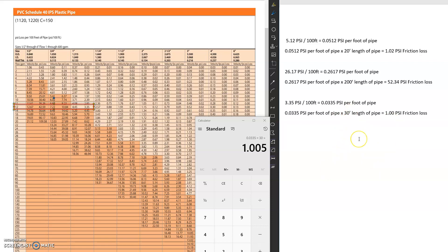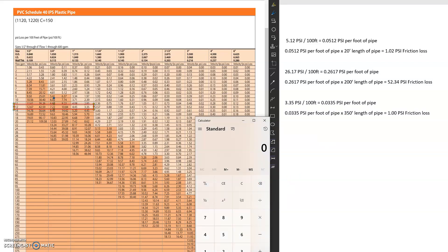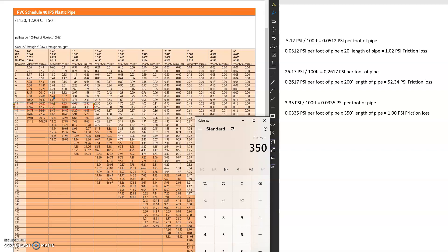So let's say I wanted to make this 350 feet. So I'm going to go back. And now for 350 feet of pipe. We're losing 11.725 PSI.